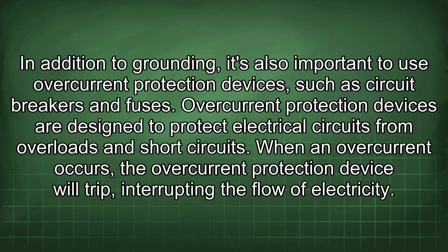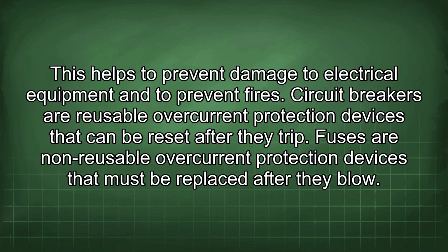In addition to grounding, it's also important to use overcurrent protection devices, such as circuit breakers and fuses. Overcurrent protection devices are designed to protect electrical circuits from overloads and short circuits. When an overcurrent occurs, the overcurrent protection device will trip, interrupting the flow of electricity. This helps to prevent damage to electrical equipment and to prevent fires. Circuit breakers are reusable overcurrent protection devices that can be reset after they trip. Fuses are non-reusable overcurrent protection devices that must be replaced after they blow.